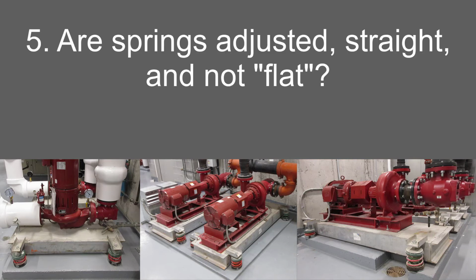Are the springs adjusted straight, not tilted or off center, and not flat? The springs are mostly okay. None of the springs was flat, that is, none of them had all of their coils touching each other, which is definitely good. On some of the bases, however, it's questionable if the proper adjustment procedures were followed since the deflections vary, but that could be partly due to short-circuiting debris. There were a couple of springs that had the load off-center, but none was too far.